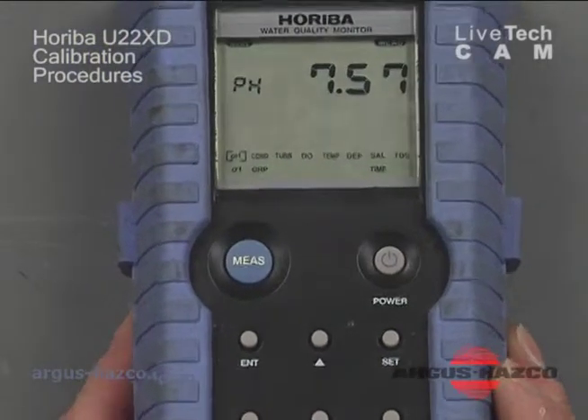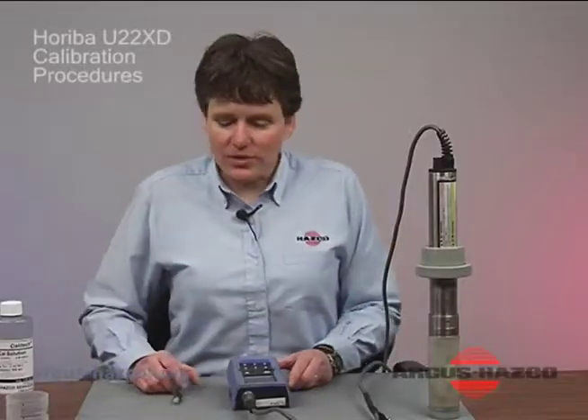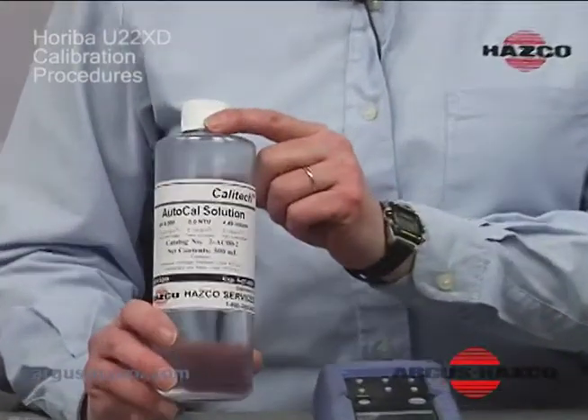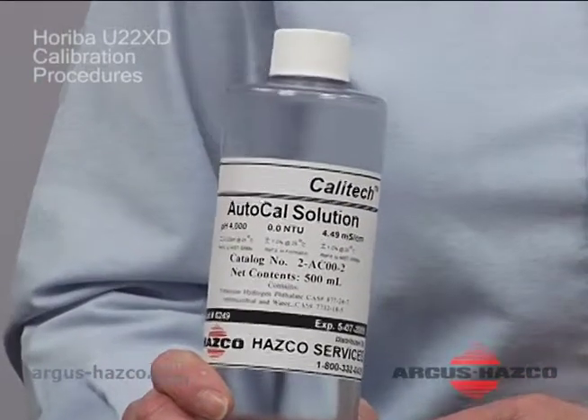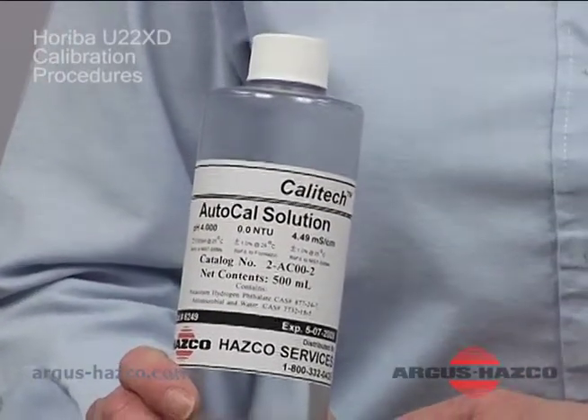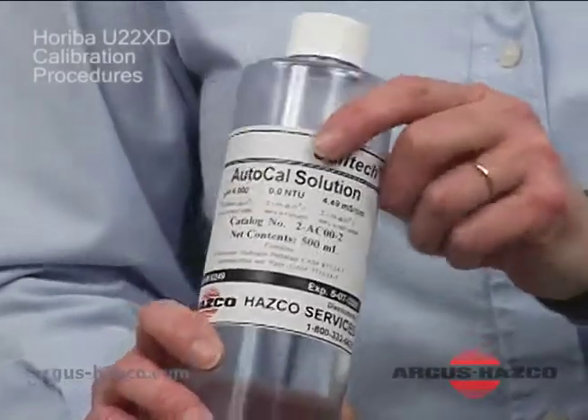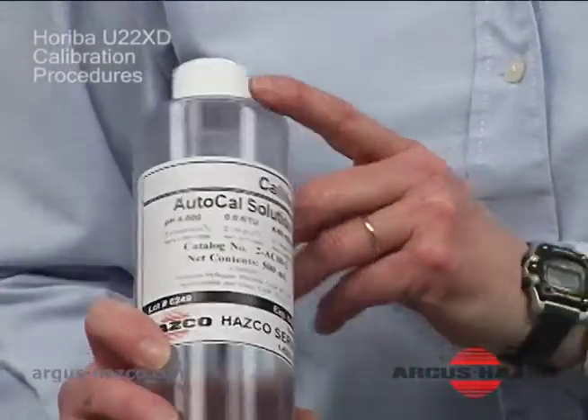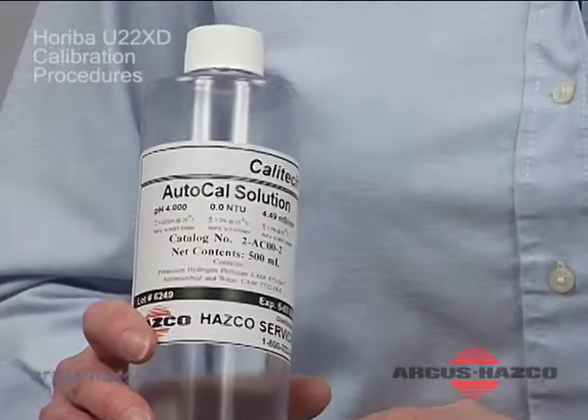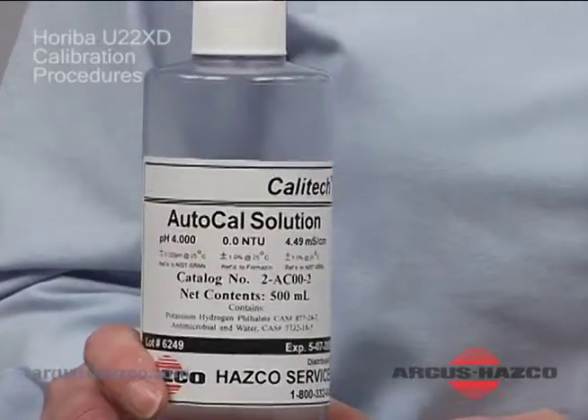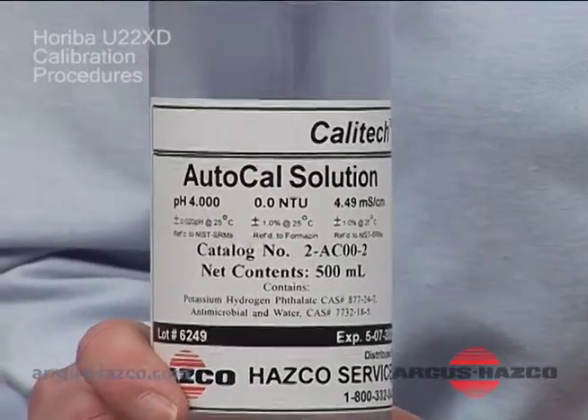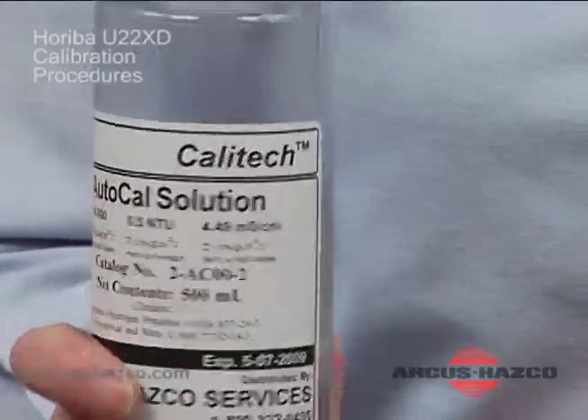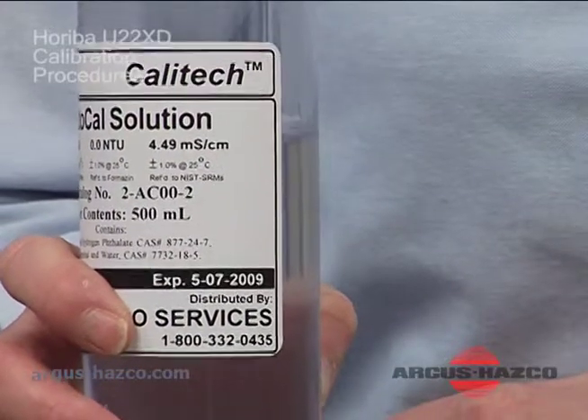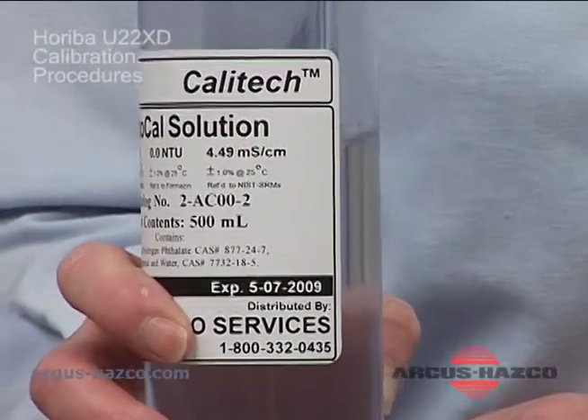Now, to calibrate this unit, we want to go ahead and use our auto calibration solution that's provided with the unit. The auto calibration solution has the parameters that we need to calibrate the U22. And again, we have pH, which is pH of 4 for calibration. And then we have turbidity, 0.0 NTU. And then we have our conductivity solution, 4.49 millisiemens per centimeter.